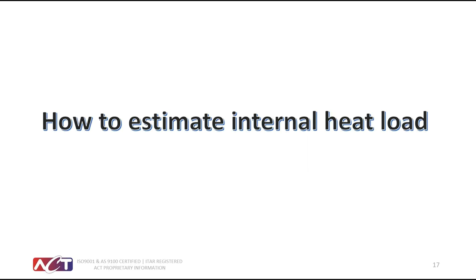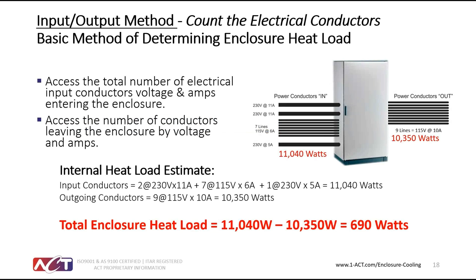So how to estimate internal heat loads? This is usually a very typical question that comes up. You ask somebody, well, how much heat do you have in the cabinet? What's producing heat? And some people know, some people don't, so we're going to offer a few methods on how to calculate that. One method, of course, is the conductor method. You can take a look at all of the conductors coming into the cabinet and the total watts that are being produced on those lines. And then you can take a look at all the lines leading out of the cabinet and the loads that would possibly or potentially be conducted on those lines, and then subtract the two. And the remaining would be the wattage or the heat load that you would have to address through some type of cooling system.